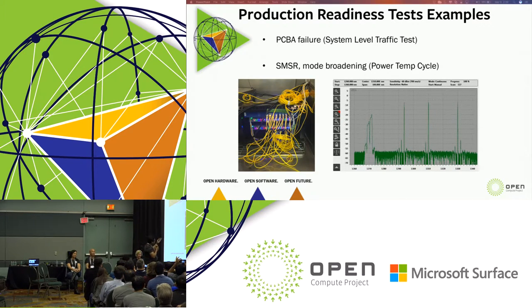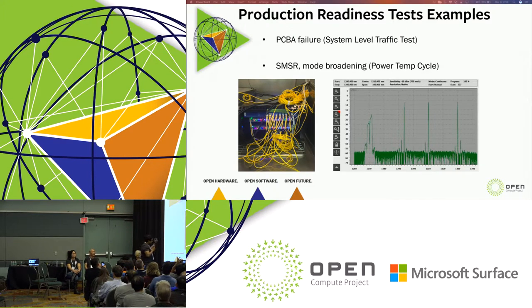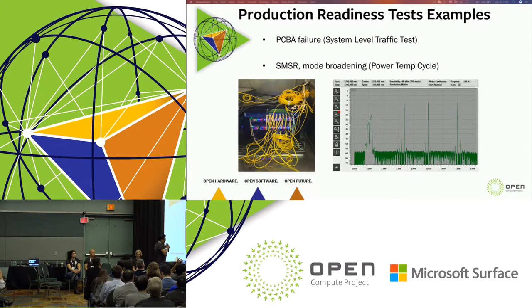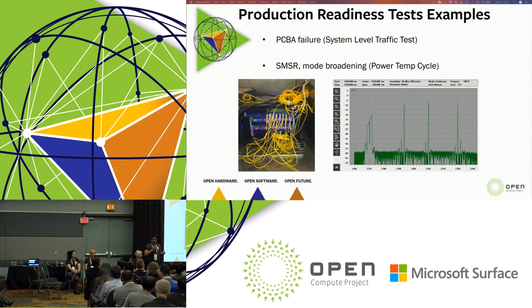These are some of the early failure mode examples we're seeing. As you can see on the right side of the picture, CWDM4 wavelengths — as Catherine mentioned — have a 20 nanometer gap between each channel. But the first channel is showing two peaks, which is failing the SMSR specification. These are the kinds of issues we are seeing, and we are working closely with all of our vendors to help them reduce these kinds of issues so we can run our data center smoothly.